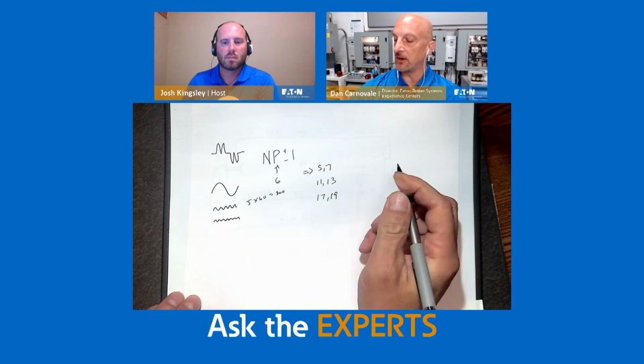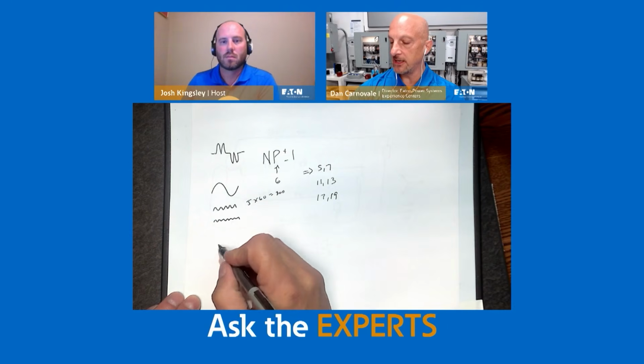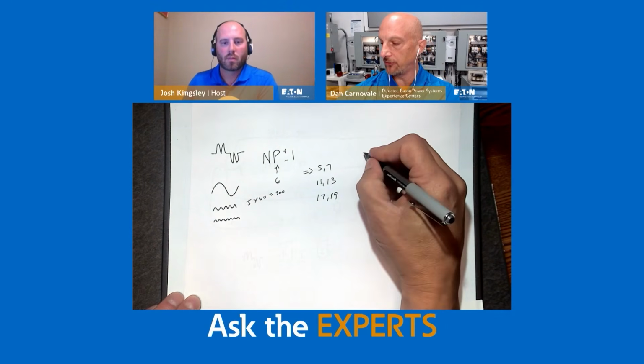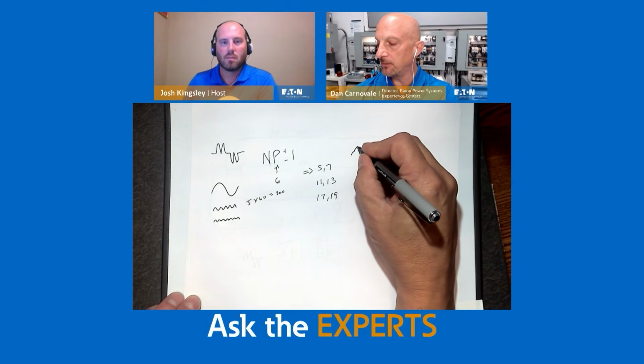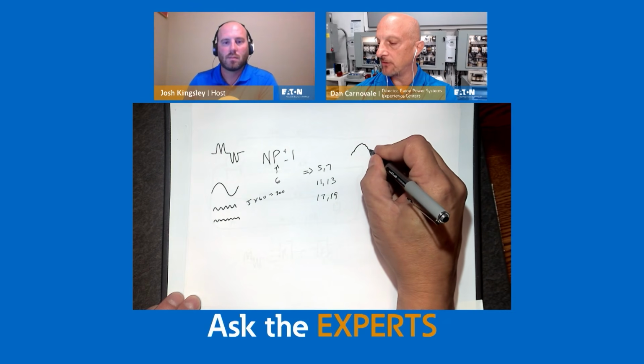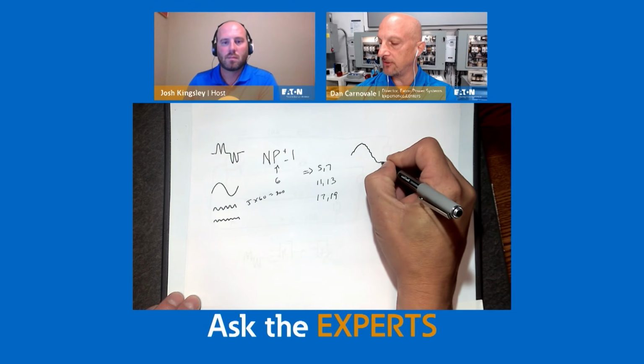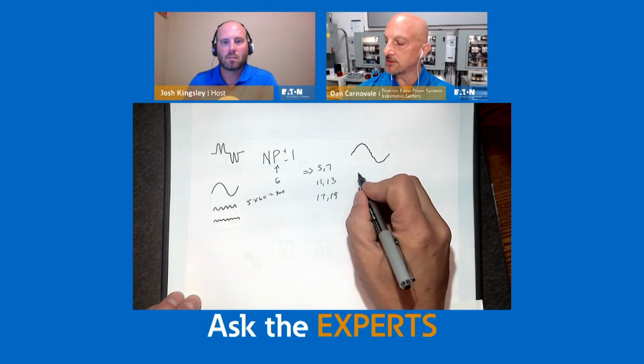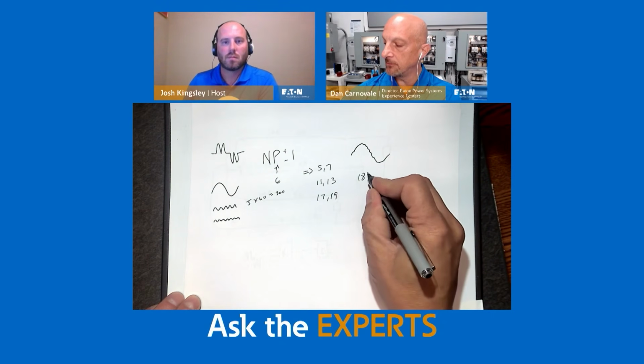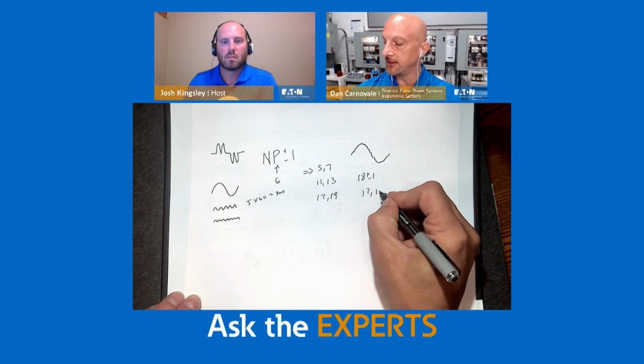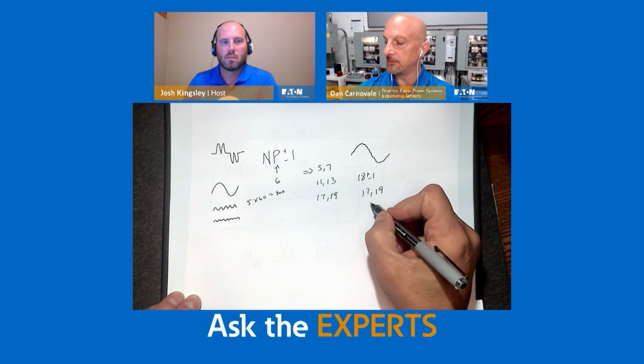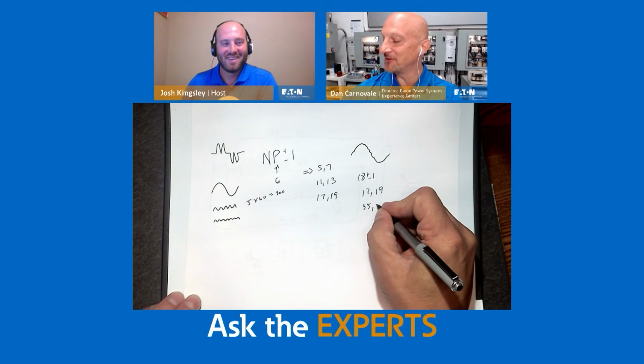So if I were to take that same equation and say, now I have an 18 pulse drive, what would be my predominant harmonic? It would almost look like I have a nice clean sine wave, and I would actually have 18 plus or minus 1, so 17th and 19th, and then 2 times 18 plus or minus 1, so 35th and 37th. You're stretching my math here, Josh.